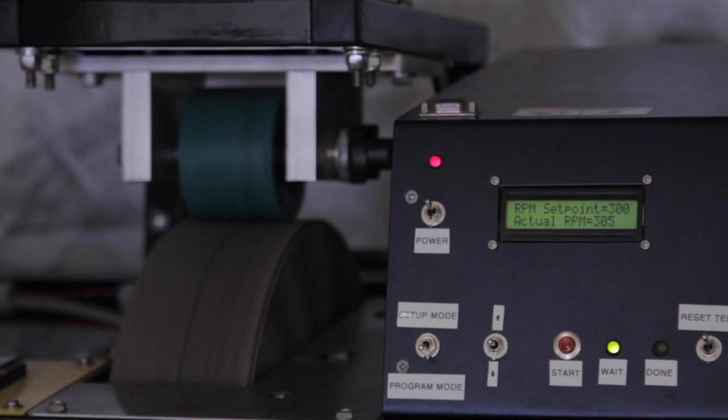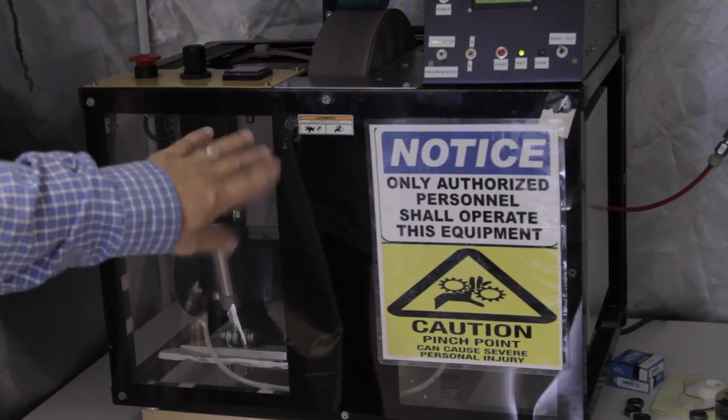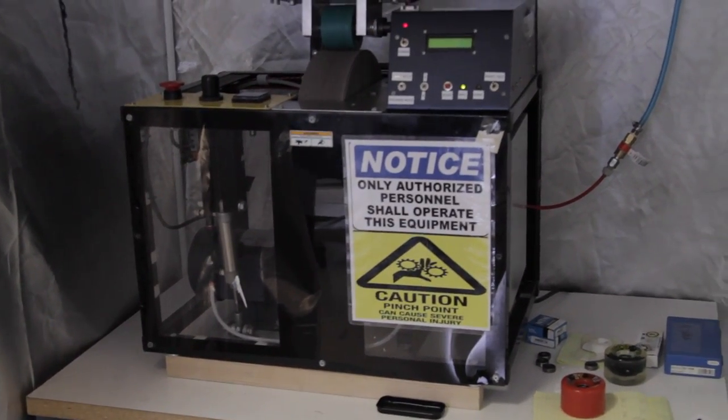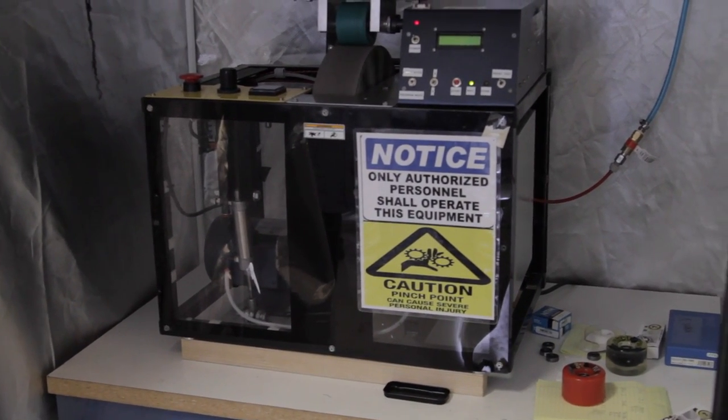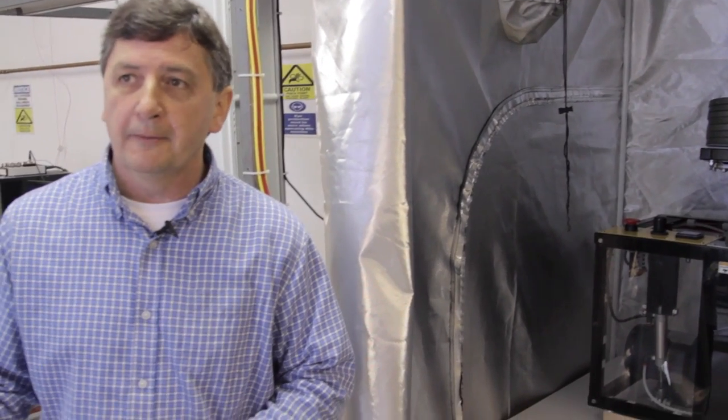So as this is going, what's going to happen is the computer will recognize it's time to go, drop away the drive wheel. There's an electric eye hiding in a dark box here with an IR sensor. And it's going to count the ticks on the side of the grinding wheel. So while this is coasting to a stop, it's going to represent about a 150 foot to 180 foot long roll. And you'd be shocked at, from bearing to bearing to bearing company, how they're very consistent, but they're all very different in how far they'll go. Depending, of course, on the build of the construction of the bearing and also the type of grease you're using and the loading of the grease or the loading of the oil.